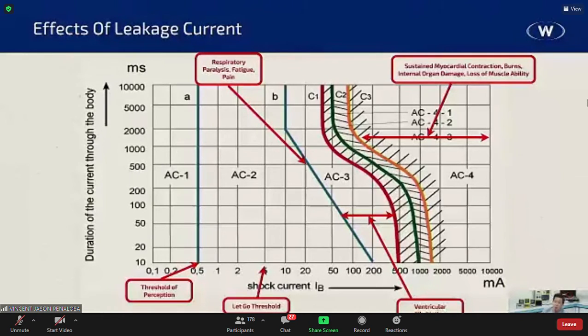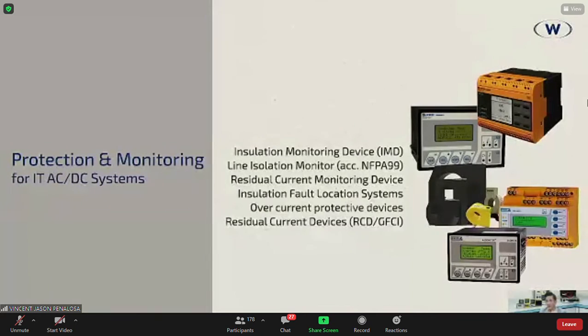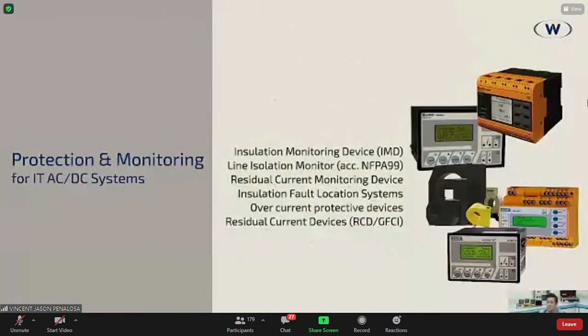So how do we protect ourselves, or how do we monitor the integrity of our insulation for ungrounded systems muna tayo, right? So you have the insulation monitoring devices. The insulation monitoring devices, you have two versions of that. One is the one you can use for AC, DC, for industrial, no? And the other one is the hospital kind of insulation monitoring device. Now, the insulation monitoring device for hospitals does the same thing, but has a few more other connections, which I will explain later. Then you have the line isolation monitor, and this is the device that they use for NFPA, right? And then you have residual current monitoring device.